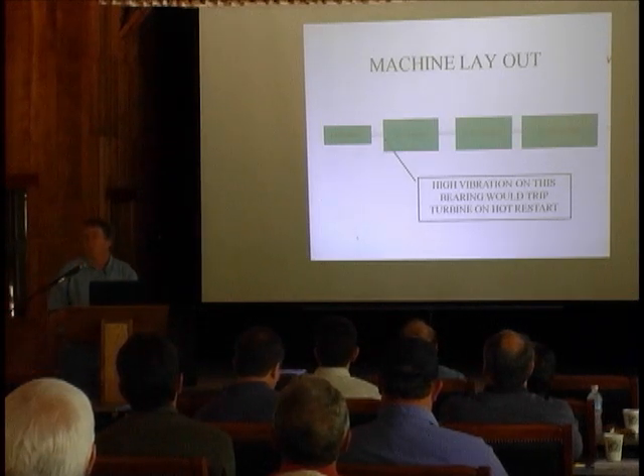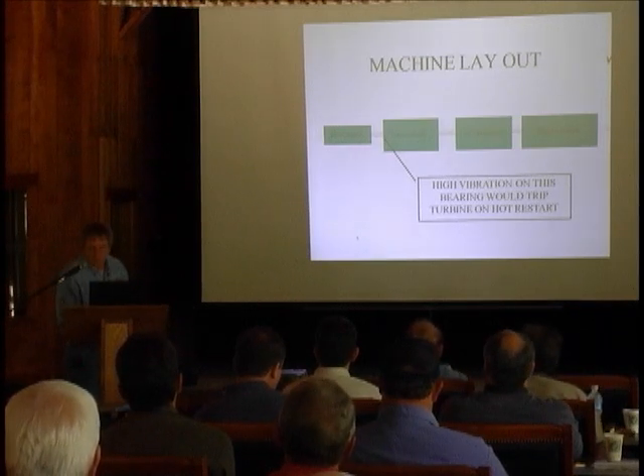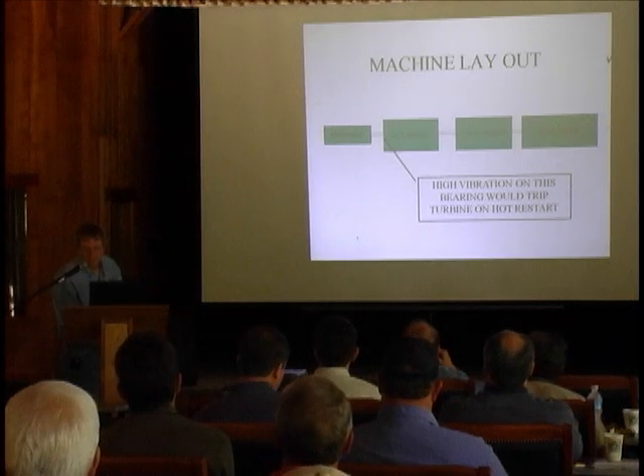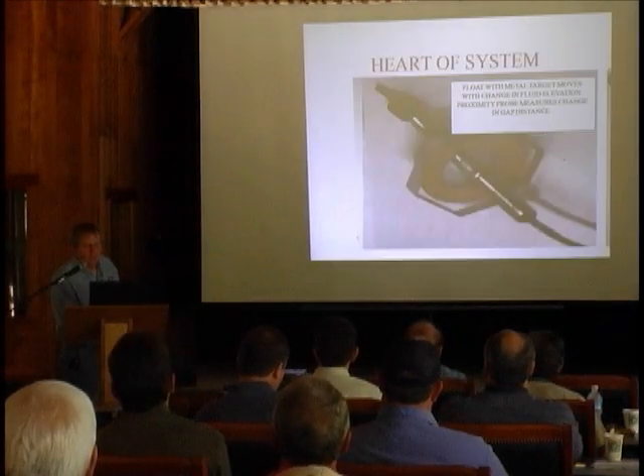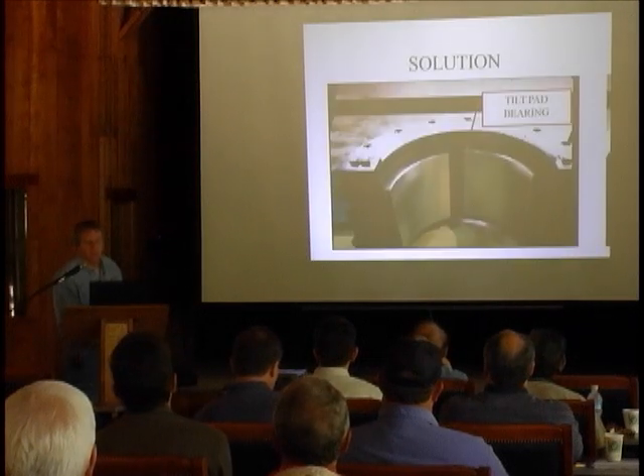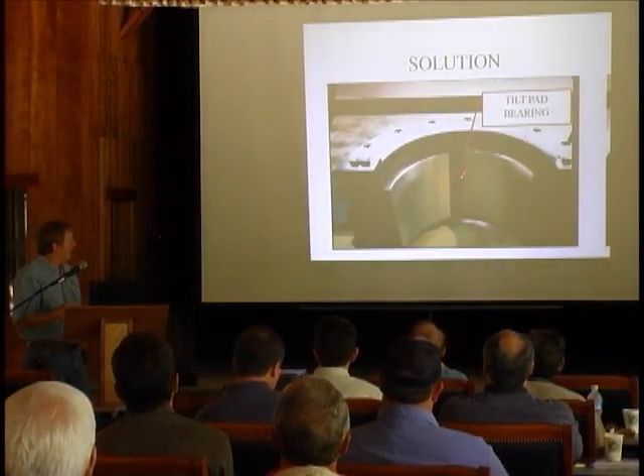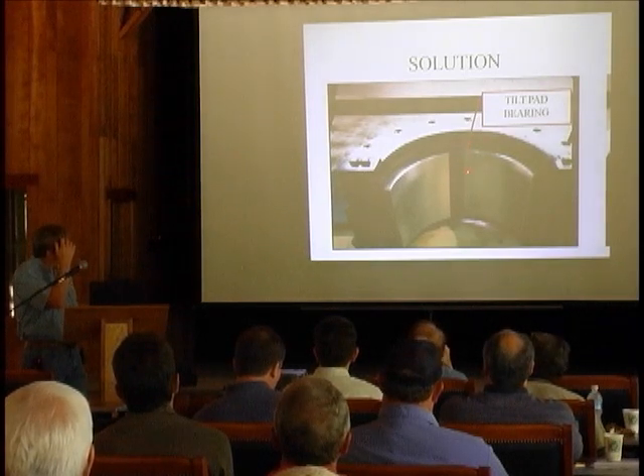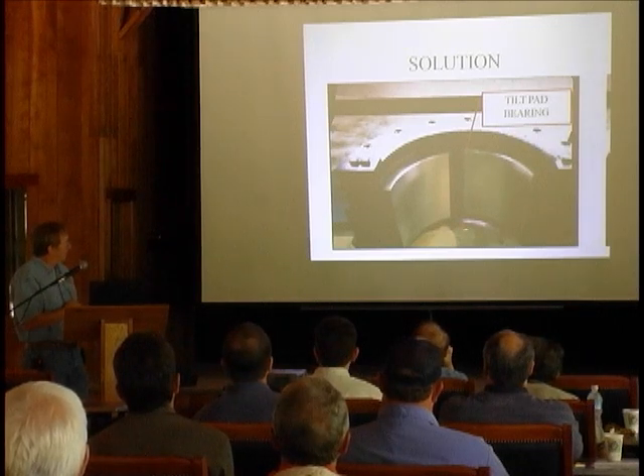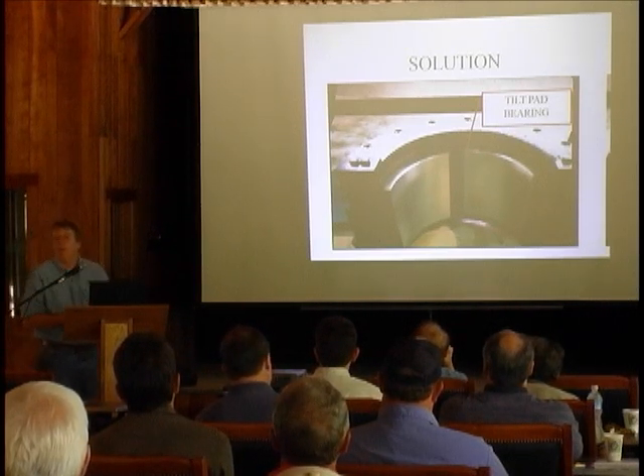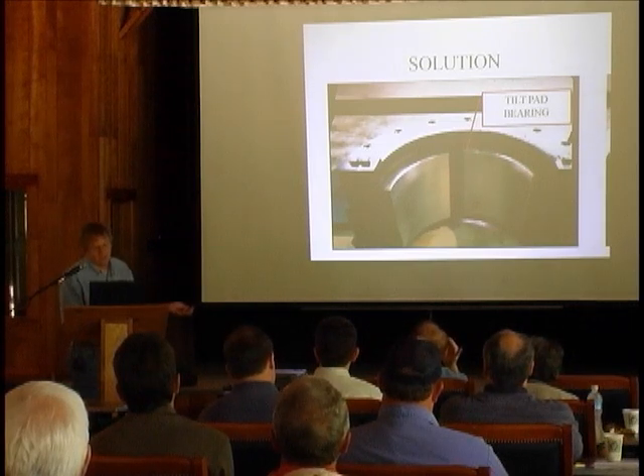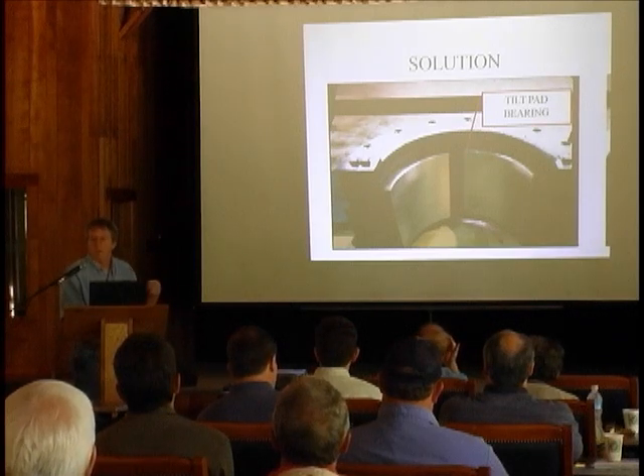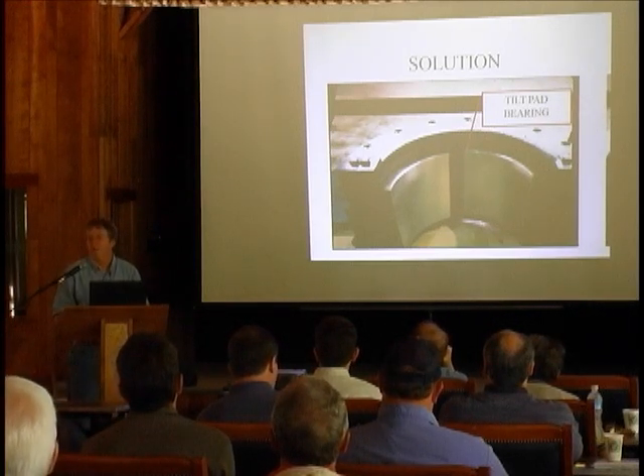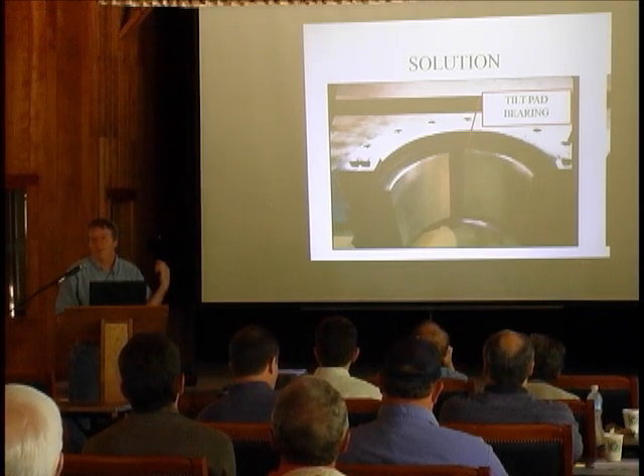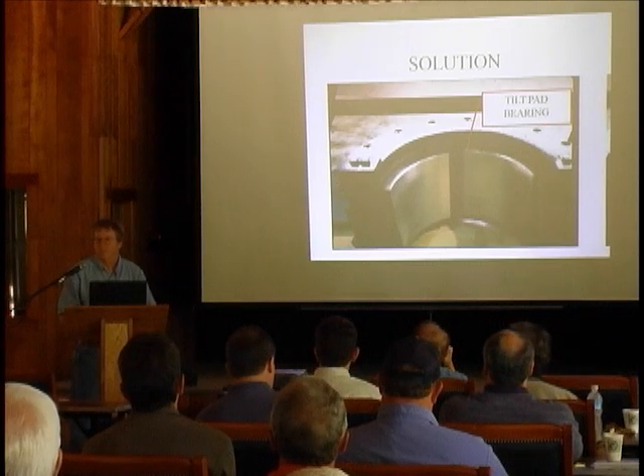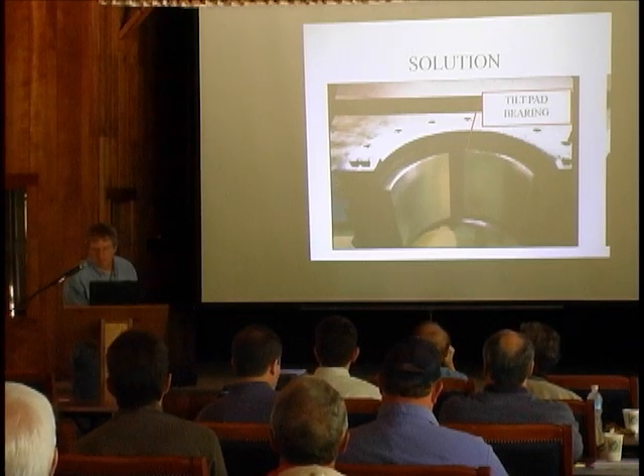And see, as a factor of that, what we did was I had them change to a tilt pad bearing. I don't know if I got a picture of that or not. Yeah, I had them change to a tilt pad bearing, and there's an outfit called Centratec out of Houston. The president of Centratec, this is his first big turbine bearing. He actually came up and installed the bearing. So we put a tilt pad bearing in there that didn't care that we misaligned it, because there's not much we can do. We're going to have condenser drawdown. We're going to trip sometimes. And you say, well, why don't you just set that bearing high? You set that bearing high on turning gear, you're going to wipe it. See? You're sort of stuck here. So I just had to put in a bearing that didn't care.